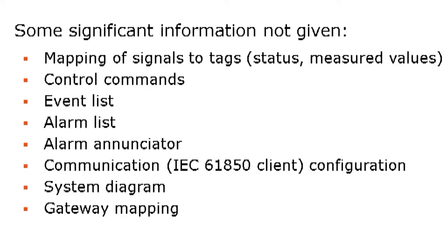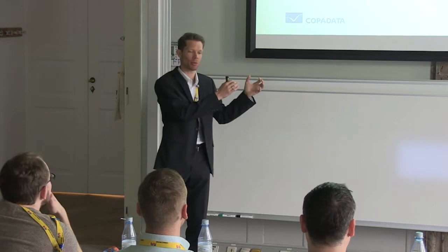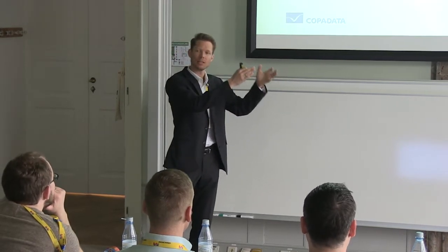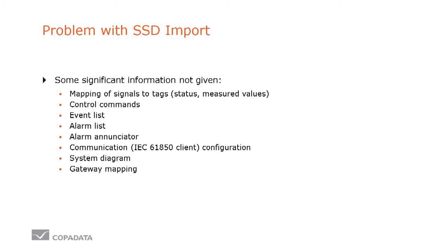Also control commands are not available in this format. Of course, event list and alarm annunciators are completely missing. Communication configuration is missing because this is the substation part, and there are other parts like the IED part and the communication part. So this will come if we use the SCD, which we see in the next slide.